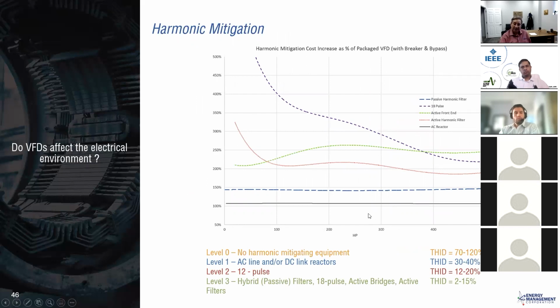And so we started developing these, thinking it was going to be short term, because we first started trying to develop a buck boost solid state topology circuit, and decided we had so many reactors in there that we just fell back to that as a quick solution. This is in that paper I talked about, which many people find very interesting. If you take a built-up or packaged VFD system that has a circuit breaker, maybe bypass, those kinds of things, that's a level of 100% with a standard AC reactor. A passive harmonic filter is about 150% from a cost standpoint. An 18 pulse drive is almost cost prohibitive at 5 times on a very small drive, as you can imagine, with that big 18 pulse phase shifting transformer. And then there are these other technologies in between.